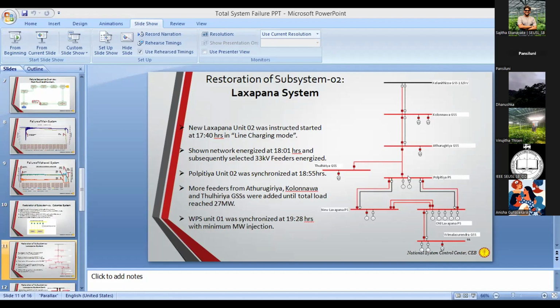Part by part. Using the first machine, it energizes only 2 or 3 transmission lines. Then those 2 or 3 lines will not generate that much reactive power. Got it? Then the first machine can absorb that reactive power and survive. That is why restoration is done as subsystems. One of the subsystems is Laxapana. From this figure you can see the Nawalaxapana line. It will energize from Nawalaxapana to Polpitiya to Athurugiriya to Kolonnawa. First it will energize up to Kolonnawa.